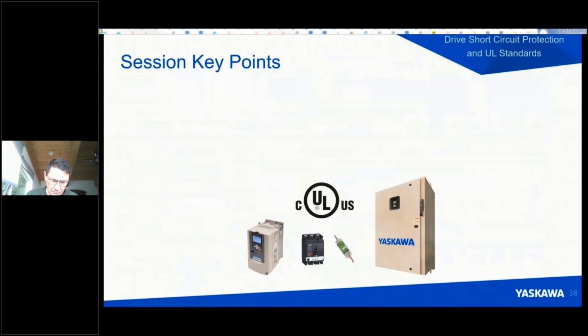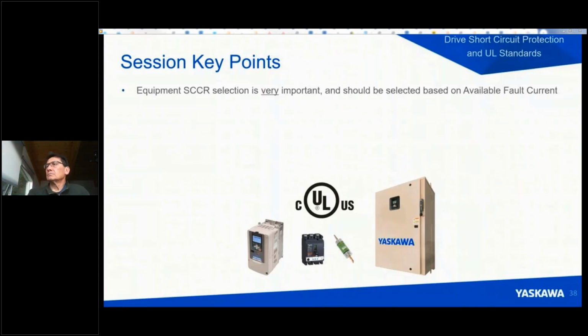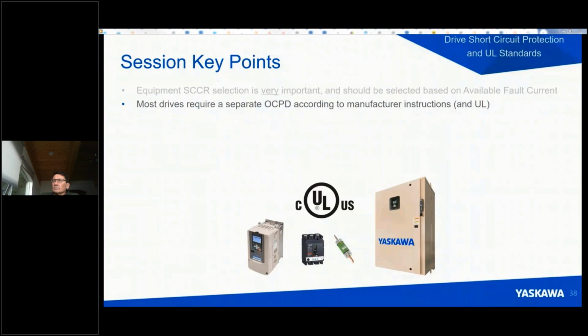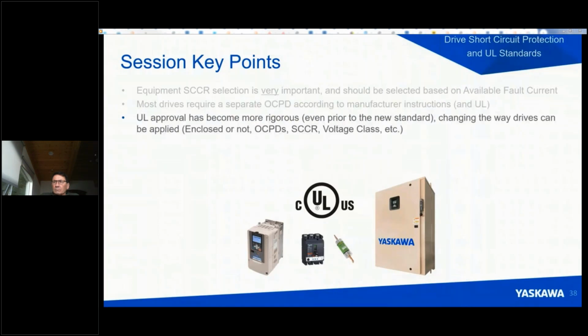So let's talk about the key points of our session. Now that actually completes all of our related topics for today, but I want to leave you with the following takeaways, the following key points. First of all, the equipment short circuit rating selection is very important and should be selected based on, again, available fault current, knowing what the available fault current is. The second thing is most drives require a separate overcurrent protective device according to manufacturer's instructions. And you will, of course, so please pay attention to instructions, and they are more detailed and more important than they were in the past.